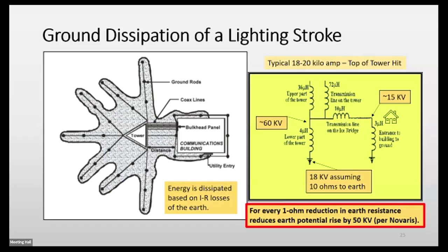You can see schematically what this really looks like - on the left, 60 kilovolts at the tower, and by the time it gets into the house, you still have 15 kilovolts coming in. That 60 kilovolts at the base of the tower drops away from the tower as it hits the earth, trying to get to ground - down to 18 kilovolts, assuming 10 ohms to earth.